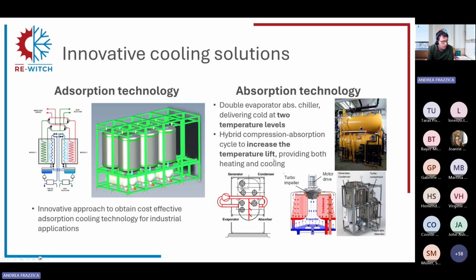This will improve the flexibility in operation, because we can maximize the exploitation of local waste heat, but also renewable power on site to drive the compressor, maximizing the operation of the chiller even in extremely harsh environments, for example when the ambient temperature for recooling is very high.